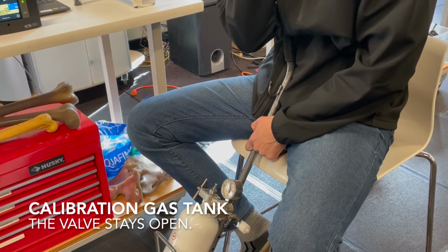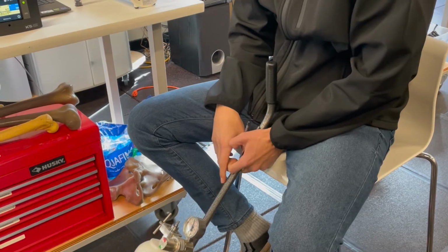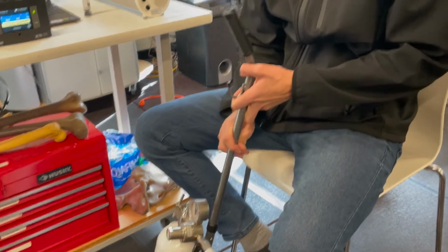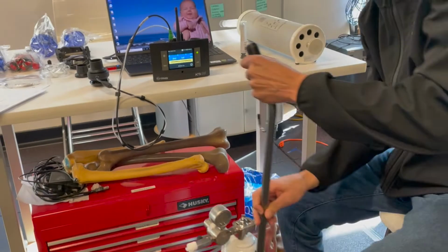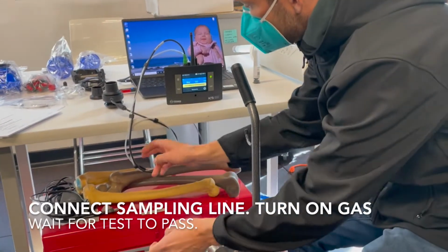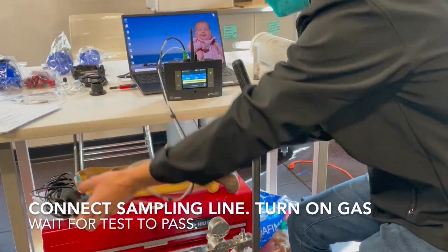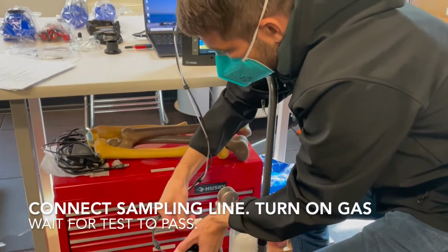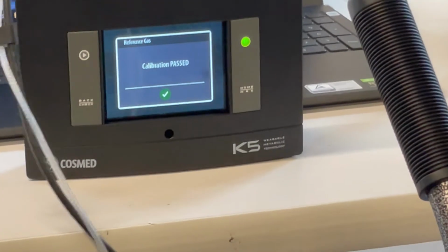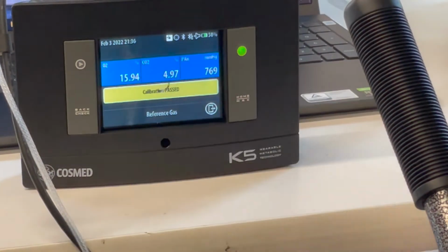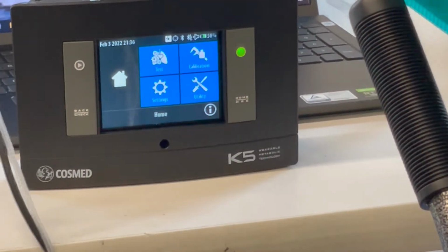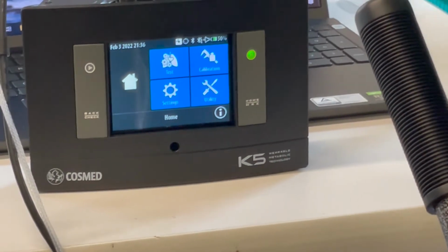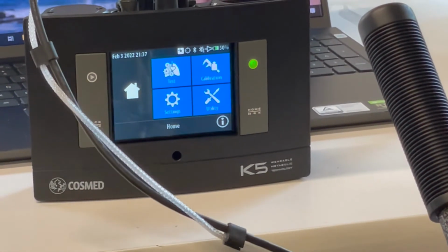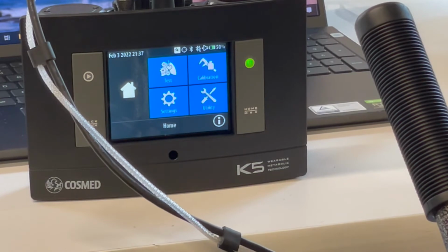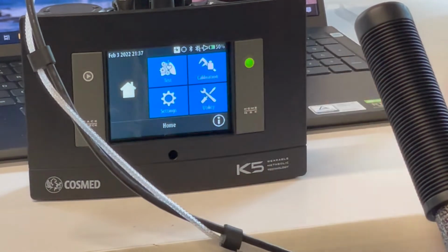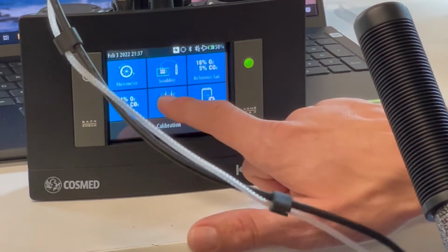Again, it just depends on how much calibrating and testing you do, but I typically say that these are good for about a year, year and a half. So it says connect the sampling line, turn the gas on, you just turn it on, and stick that guy right in there. Calibration passed. Good. So just pull that guy out, turn that off. The calibration would take a little longer if it was breath by breath because it would have added the delay in there. So we're gonna go back and we're gonna do the delay now.